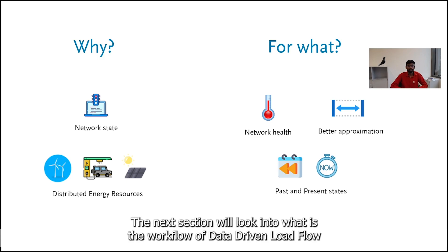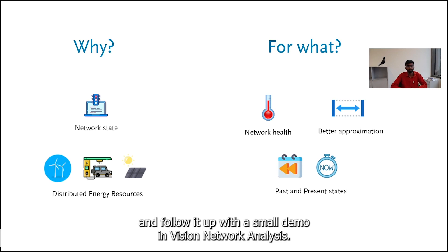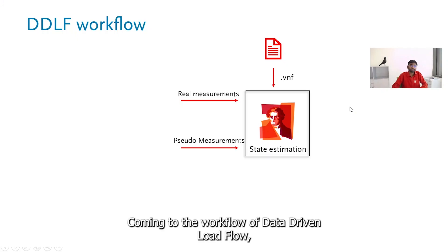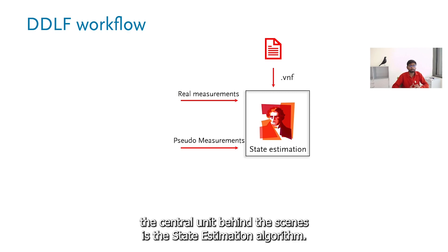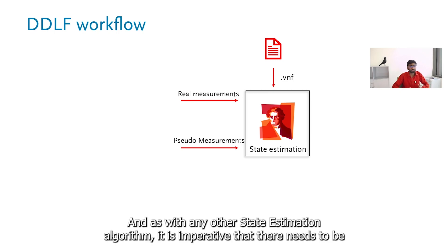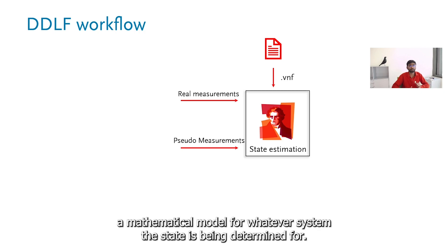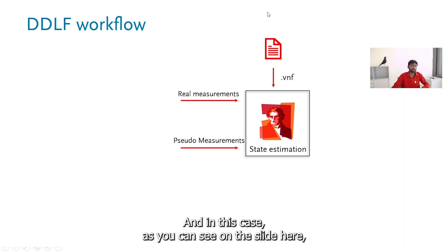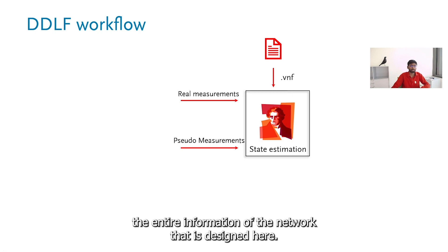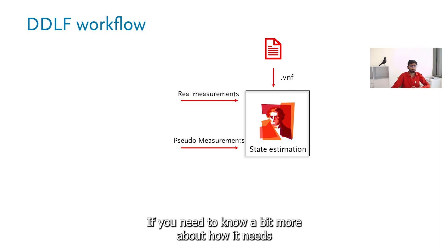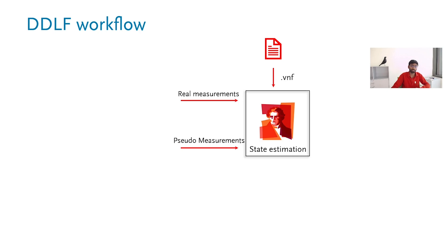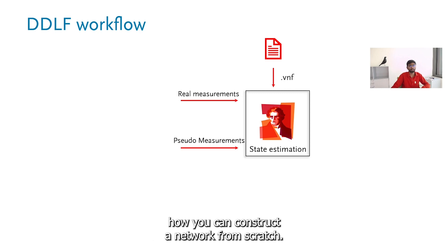Now in the next section we'll look into the workflow of data driven load flow and follow it up with the small demo in vision network analysis. Coming to the workflow, the central unit behind the scenes is the state estimation algorithm. In vision network analysis we use the weighted least square algorithm for this module. As with any other state estimation algorithm it is imperative that there needs to be a mathematical model for whatever system the state is being determined for. The .vnf is basically the vision network file format which comprises the entire information of the network that is designed here. If you need to know a bit more about how it needs to be designed, you can look into one of our previous videos getting started with vision network analysis.